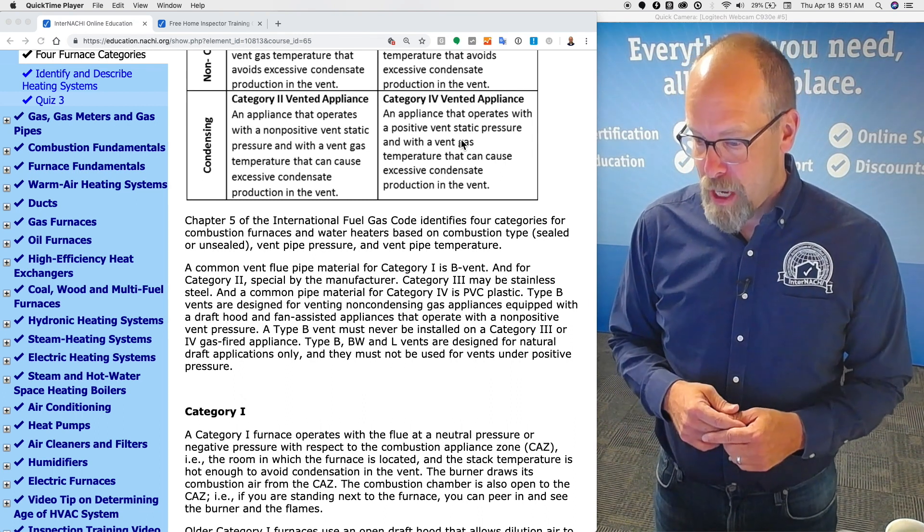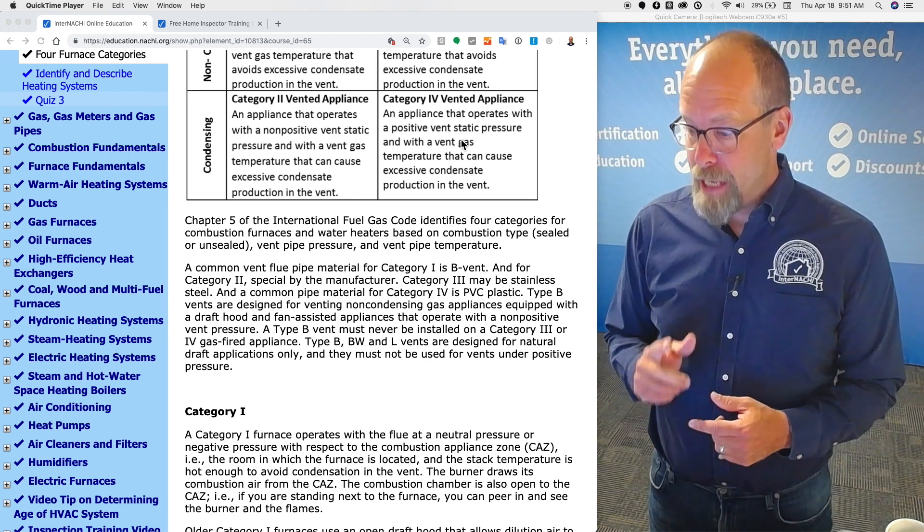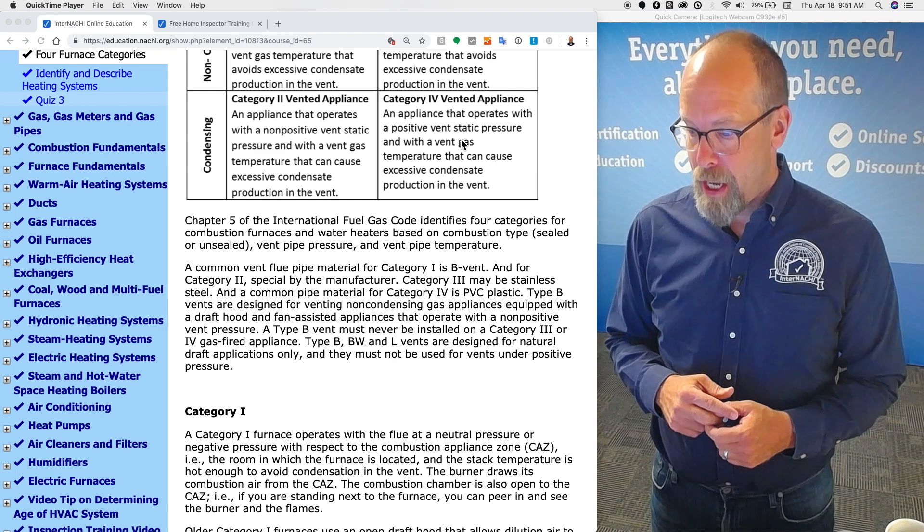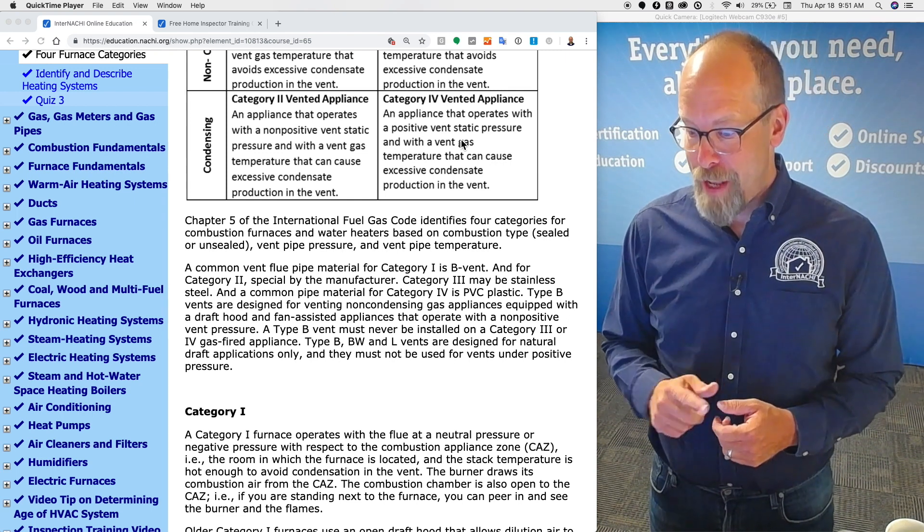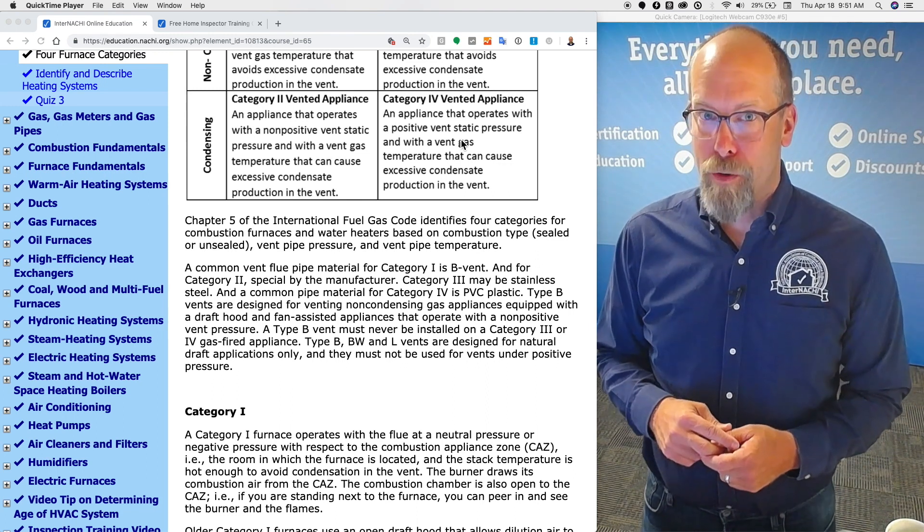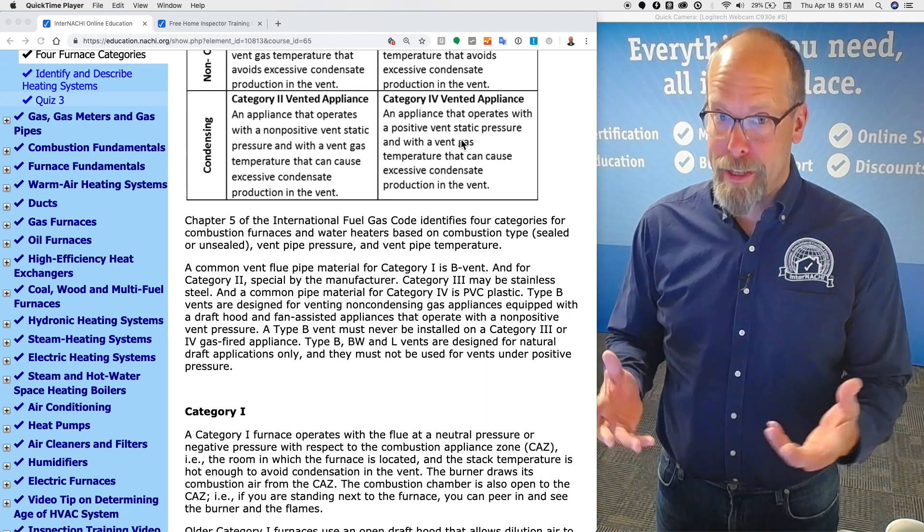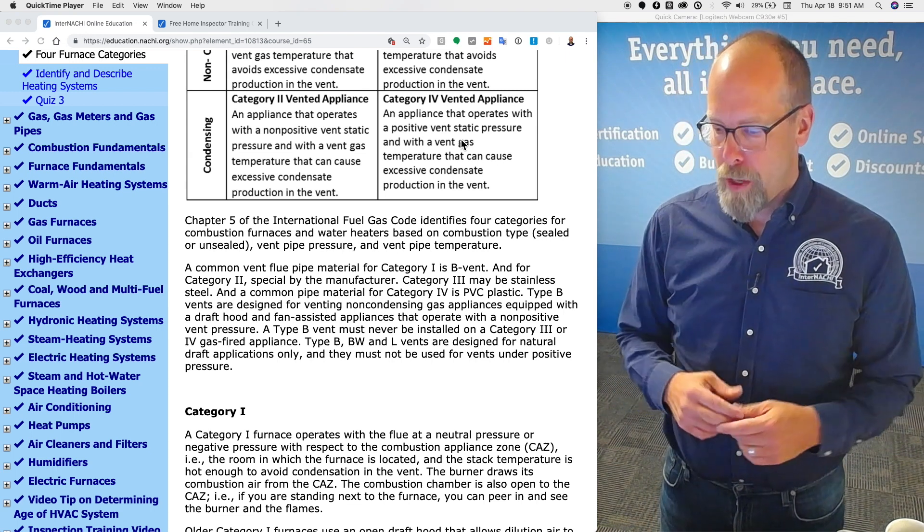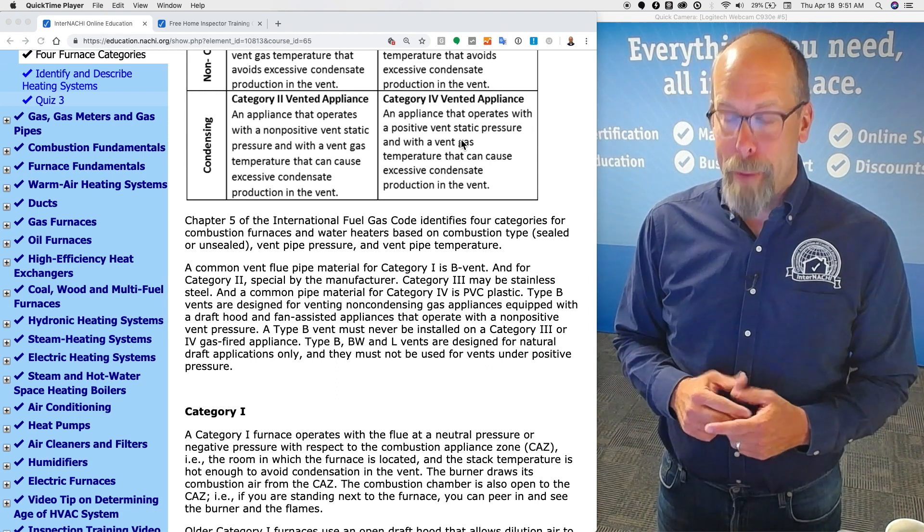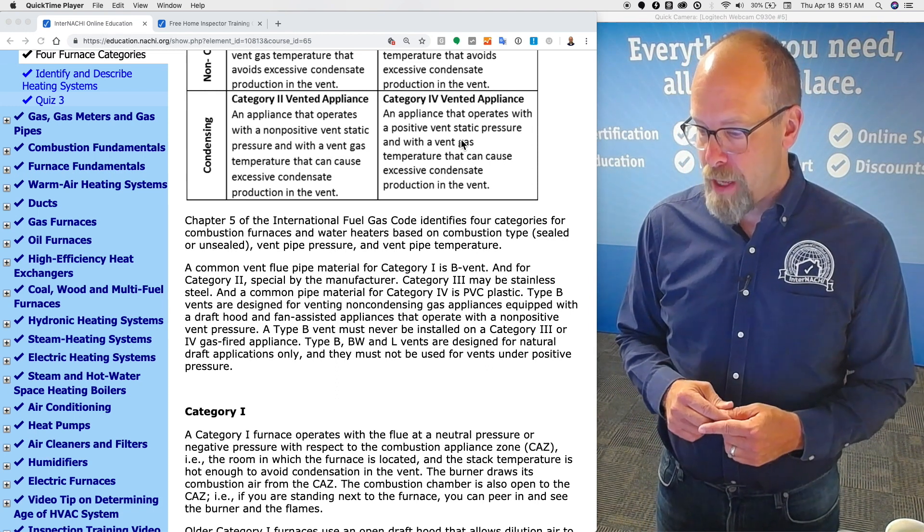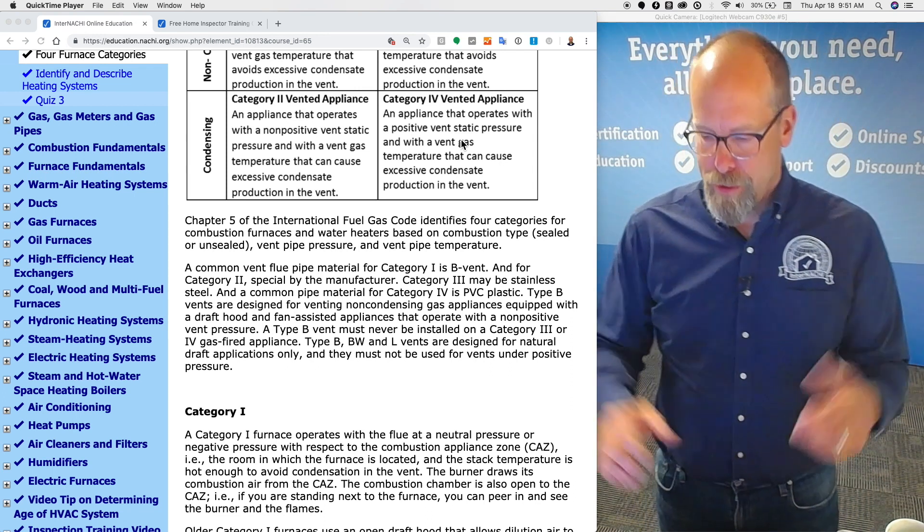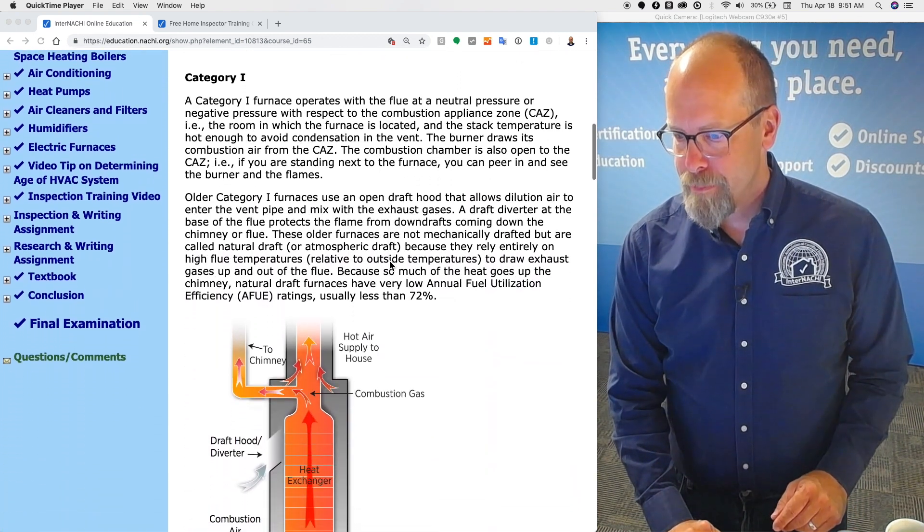Type B vents are designed for venting non-condensing gas appliances equipped with a draft hood and fan assisted appliances that operate with a non-positive vent pressure. A type B vent must never be installed on a category three or four gas fired furnace appliance. Type B, BW (that's the oval one), and L are designed for natural draft applications only. They must not be used for vents under positive pressure. Carbon monoxide will come through the pipes. It'll be hazardous.